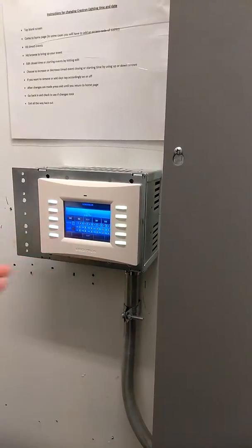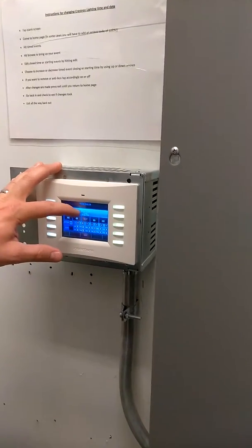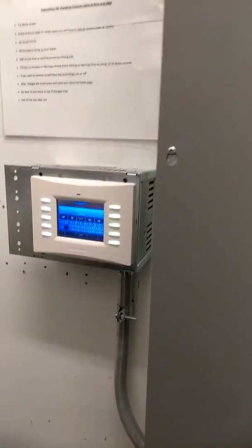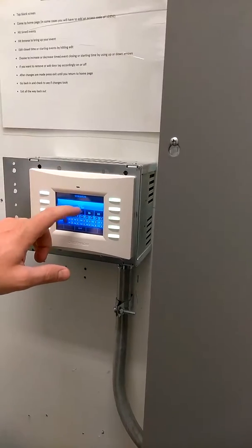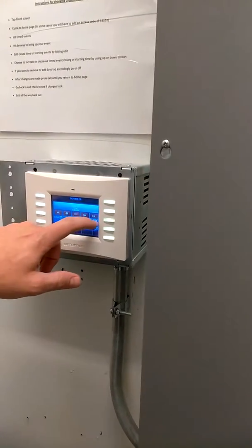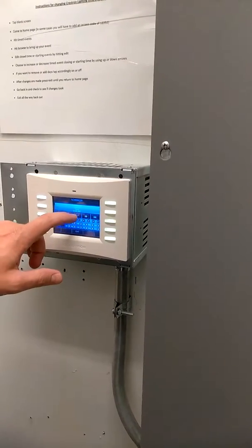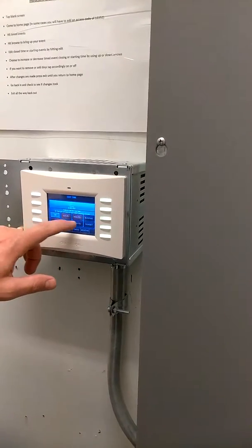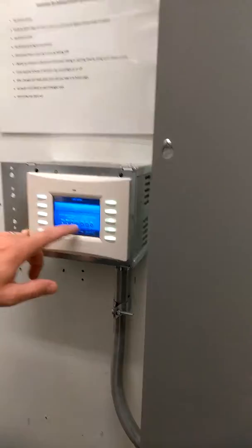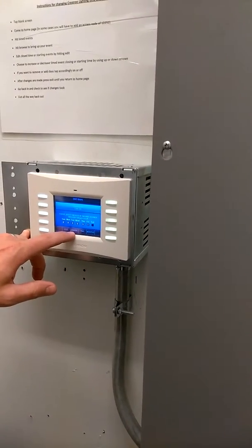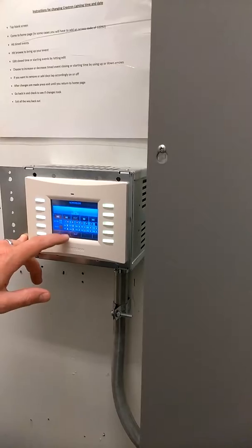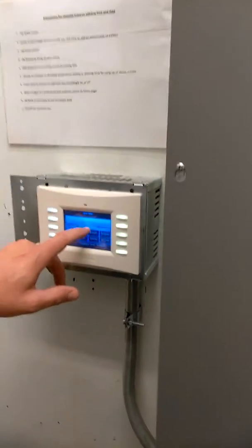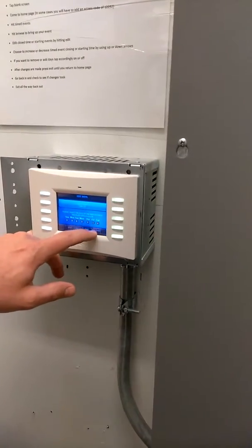This event's called Floor 2 Off. This is saying at 9 p.m., Floor 2 lights will turn off. And as you know, Floor 2 and the cafe are separate. The next event is called Cafe On. So at 6 a.m. every day of the week, the cafe will turn on. Let's say we don't want that turning on Saturday because no one comes in, hypothetically. You can hit edit, then hit days, uncheck Saturday, and then hit exit. So you see now the Cafe On event will never fire on Saturday, but it will fire all the other days of the week. Okay.